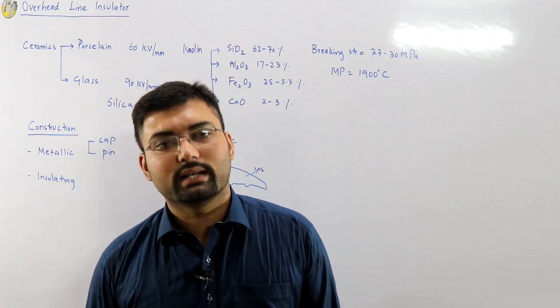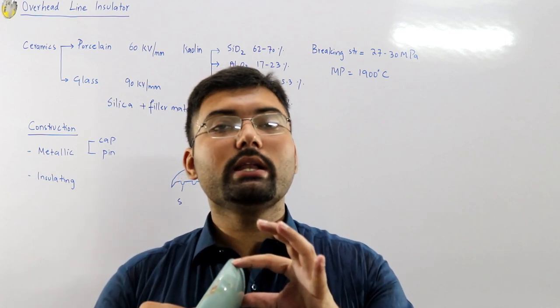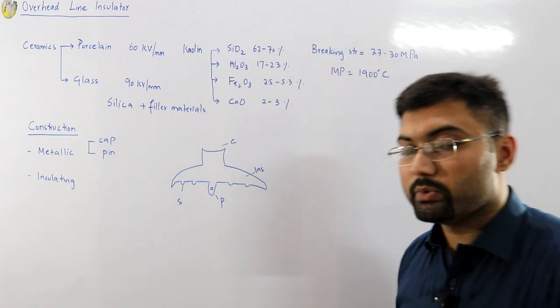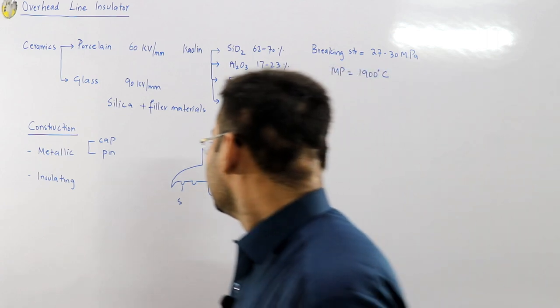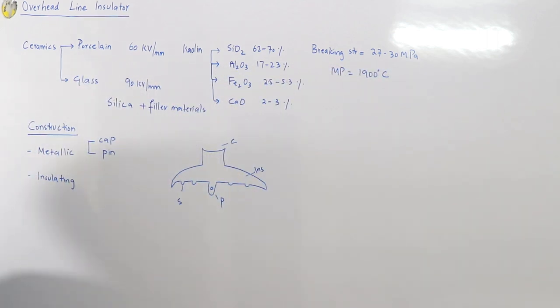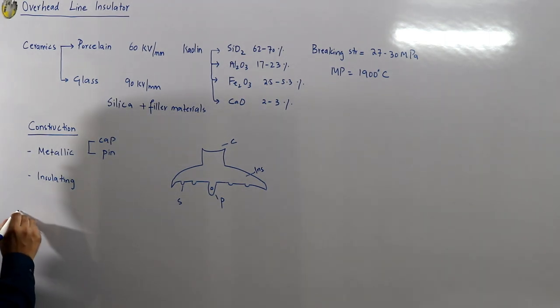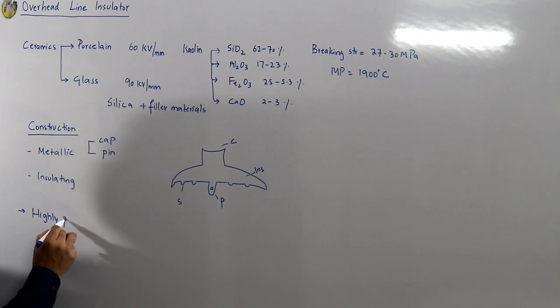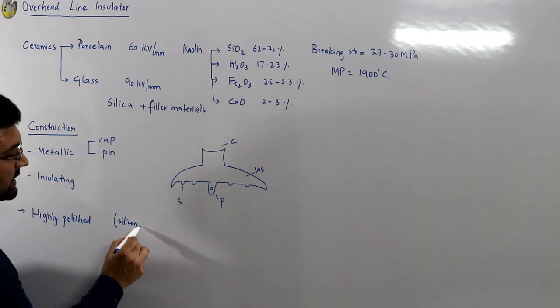Since you have two metallic contacts with a dielectric in between, this acts as a capacitor — we will model an insulator as a capacitor in the next video. The insulator is made highly polished and clean, and the final finishing for the porcelain insulator is given by a compound called silicone grease.